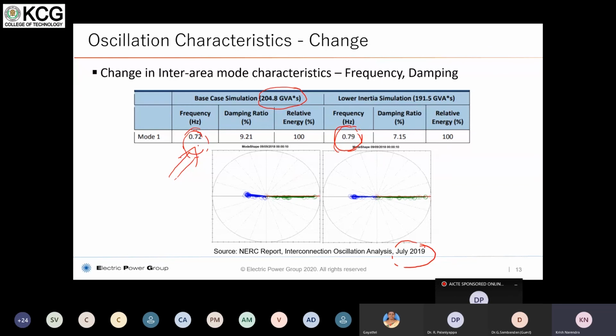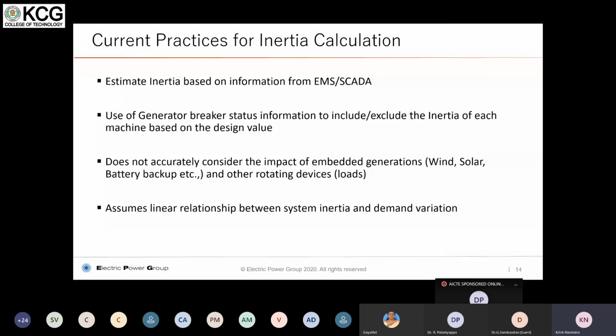So what is the current practice of inertia calculation? Currently, they estimate the inertia based on information from EMS and SCADA. With SCADA, every 10 seconds or 20 seconds or 1 second, depending on the kind of SCADA you have implemented, they get the generator breaker status. That means for all the synchronous generators connected in the system, they get the breaker statuses and include their inertia constant based on the design value. So as you can see, first of all, we are making a mistake by utilizing the design value. It may not differ too much from practice, but when it is put into the system and all the rotational masses are connected to the shaft, there will be some variations from the design value. And that is one aspect.